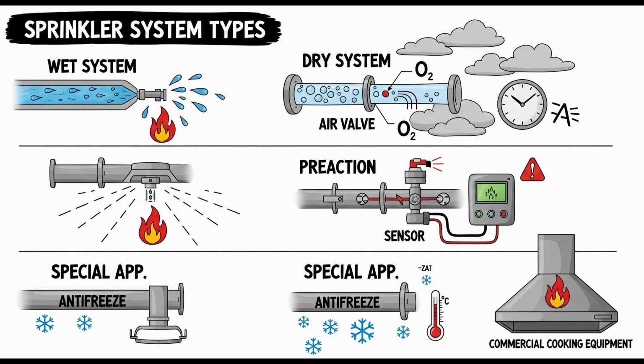Table 8.2.3.6.1, starting from normal air pressure and with the manifold fully opened. So you're physically proving the system can deliver water fast enough for the expected fire size, not just to one point. Exactly. If you meet the requirements using this manifold test method, you don't need to meet the 60-second rule or the calculation rule. It's an alternative path to compliance. Flexibility in how you prove performance.